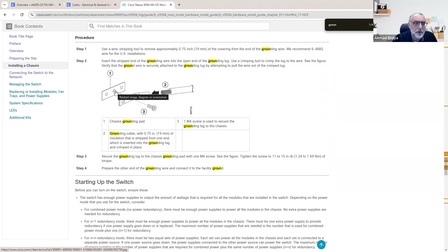On the other side, you need to connect it to the rack. This way you make sure the chassis and the rack are at the same voltage. Then this rack is connected to the raised floor, connected to all other racks in the center, and you end up having all the devices, active or passive, in your data center connected to the same common ground, with no voltage difference between them.